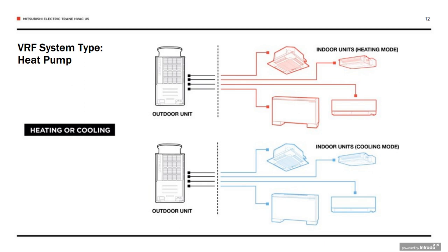Now, let's dig a little bit deeper at the differences between the 2 types of systems that you will find within VRF. VRF systems can be heat pump or heat pump with heat recovery. Shown here is the heat pump option that allows for heating or cooling. Typically, this is going to happen in spaces where the load profile is uniform. Think common areas, some entryways, maybe an auditorium. And again, there's a lot of flexibility still within this system, in that a system that is calling for cooling can have a set point of 70 degrees or can have a set point of 76 degrees, still in cooling, but still delivering the comfort that person needs.